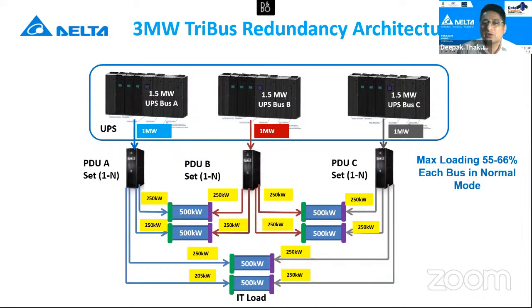Now, for example, out here to meet 3 megawatt, in the previous example, you had to have 3 megawatt on two buses. And out here, you need to have 1.5 megawatt on 3 buses to create the same architecture and the same end result, which is the 2N to your customer load. And that is more critical. You are committing a 2N architecture with an uptime requirement to a customer. That is met by this architecture also.